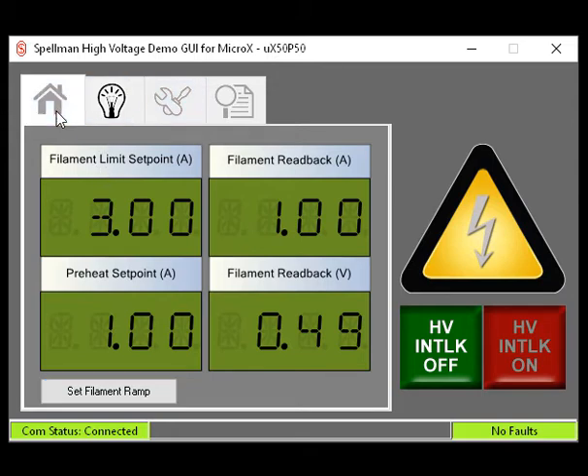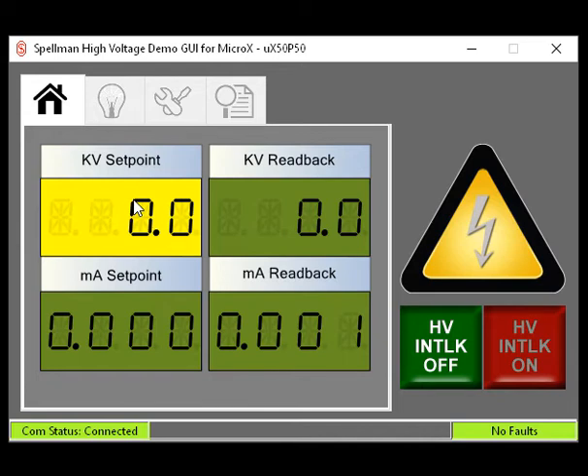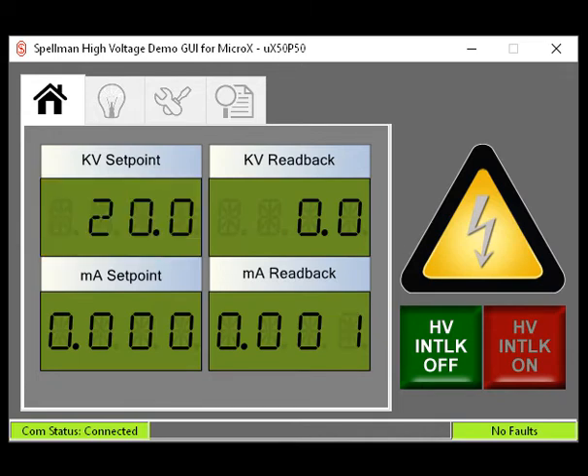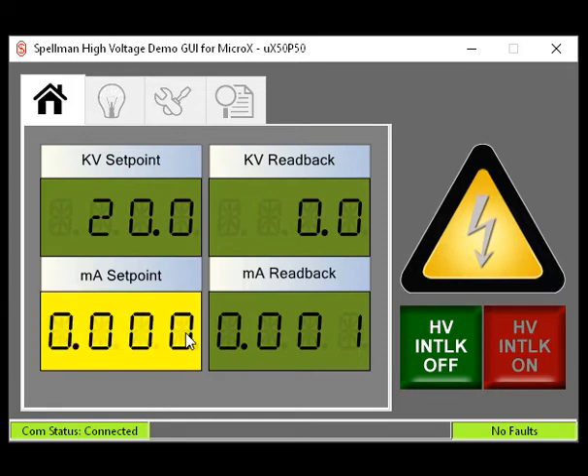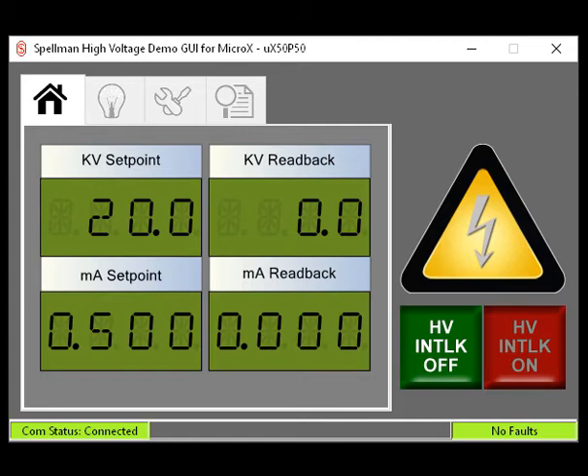The Home tab, indicated by the house icon. This tab is where you set the KV set point and the MA set point. Click on the respective box and type in the desired value, then use Enter to exit. KV and MA readback displays are provided to monitor the actual KV and MA when the high voltage is enabled. If you have entered all the appropriate set points and all high voltage and X-ray safety related issues have been addressed, you are ready to enable the high voltage.